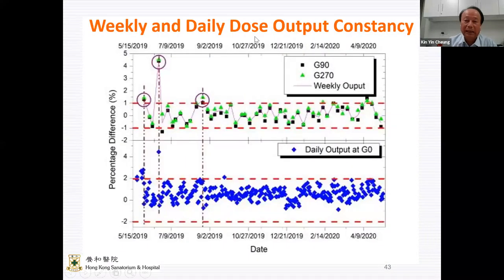And this is typical of the data we have over the past year. On top, the green and black dots are the weekly output dose measurements, and they fall within 1%. And on certain occasions, we do need to adjust the output slightly. And the bottom is the daily constancy output. It falls within 2%, except on three occasions when we needed to adjust. When we find a daily output exceeds the 2% tolerance, we do a more accurate dose check. And when that is also off tolerance, we do an adjustment and so on.